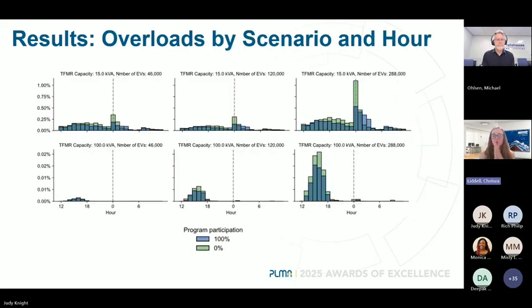And then this just shows the timing of those overloads during the day and compares a smaller transformer to a larger transformer. So that top row is a 15 kVA transformer, and each of the columns, from left to right, is adding more and more EVs. So if we focus on the top right graph, we can see this small transformer with the most EVs. Those blue lines are the number of overloads with the program, and the green bars are without the program.